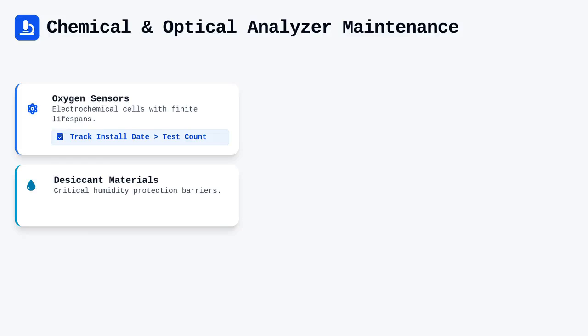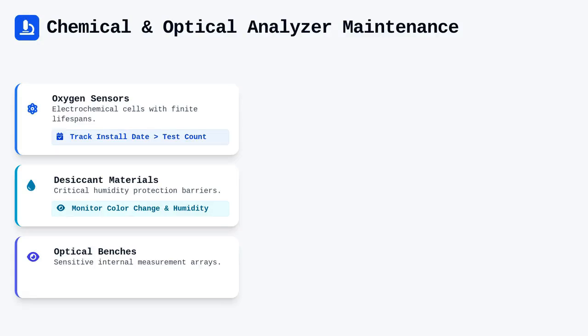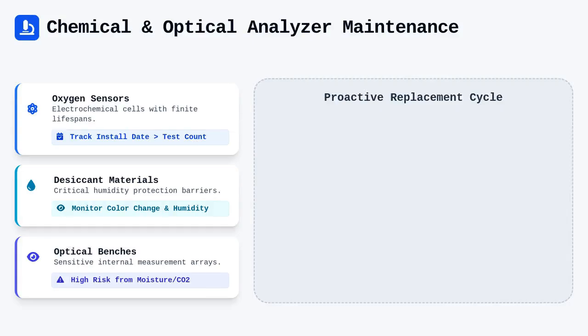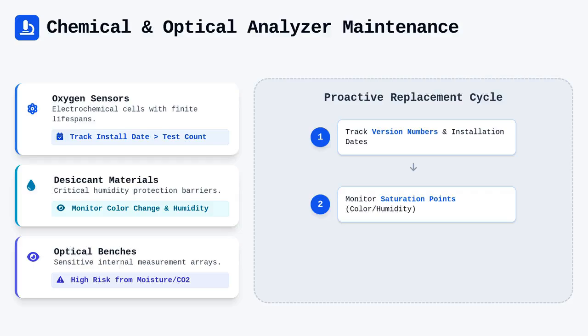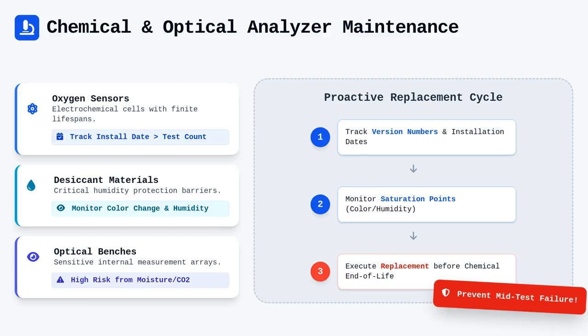Similarly, the desiccant materials used to protect these sensitive analyzers from humidity must be monitored and replaced before they reach their saturation point. If the desiccant changes color or the system internal humidity levels rise, you are already risking damage to the internal optical benches. Implementing a tracking system for these component version numbers ensures that you aren't caught off guard by a sensor reaching its chemical end of life during a patient test.